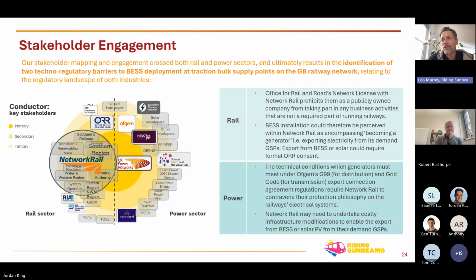We also found some major techno-regulatory challenges around integrating storage that's capable of interacting with the grid as well as providing useful services to the railway. These can be summarized as a fundamental incompatibility between the regulatory requirements of generators connected to the grid—and battery energy storage is classed as a generator—and the protection philosophy that operates on the railway. There are requirements on you as a generator that can't be met under the current protection arrangements on the railway.